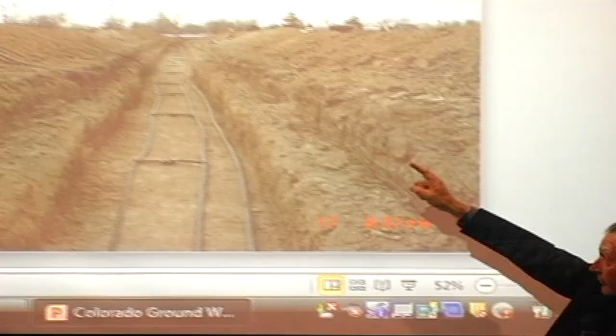Okay, so after we drill these holes, if you take a look at this right here, that represents the top of 2-inch-and-a-quarter pipes coming out of the top of a 500-foot drilled hole. Then we go in and excavate this trench and manifold these together horizontally in a reverse return configuration, with the pipes being sized up and then sized back down, so basically these circuits self-balance. We want to make sure we push just as much water to the very last loop as we do to the first loop. That's where the balancing comes in.